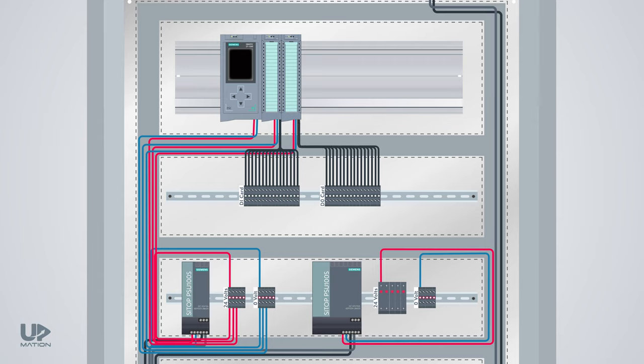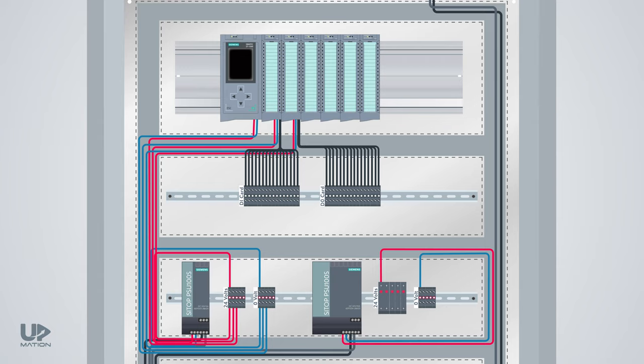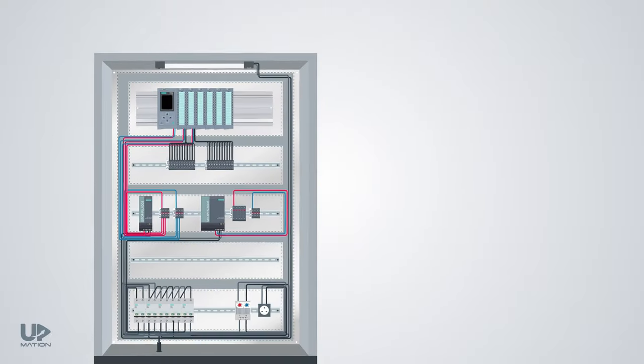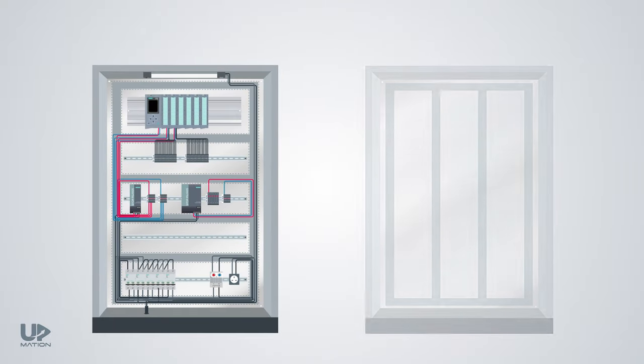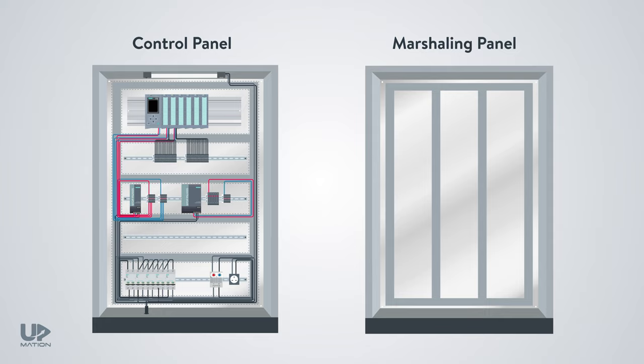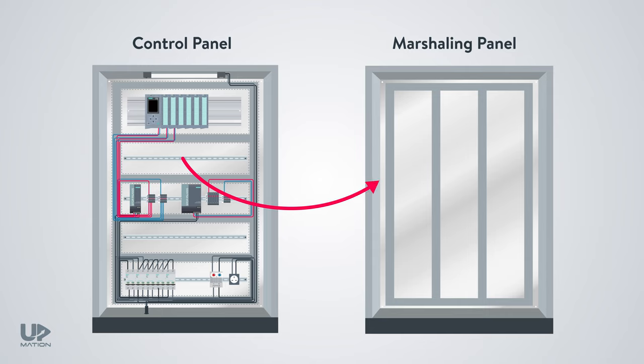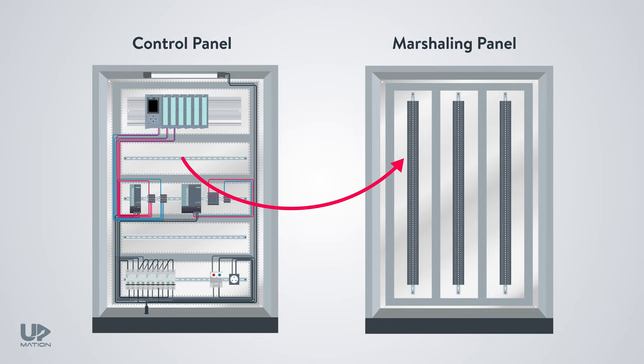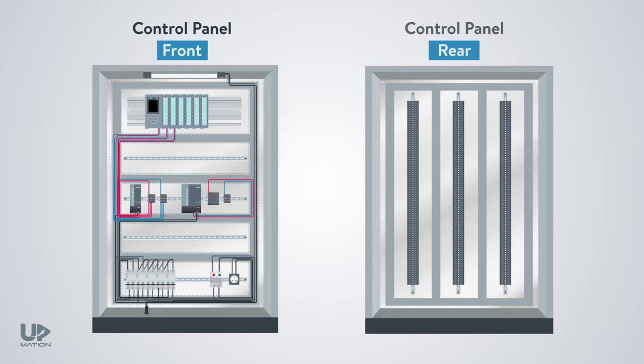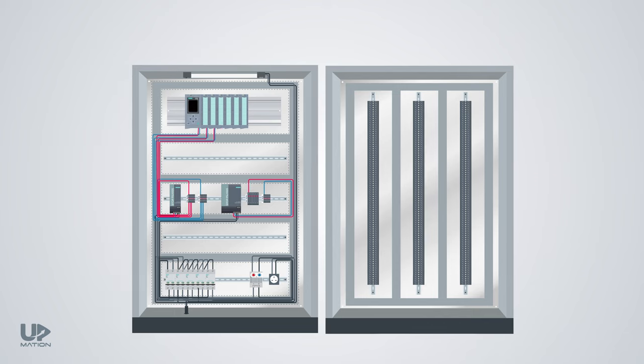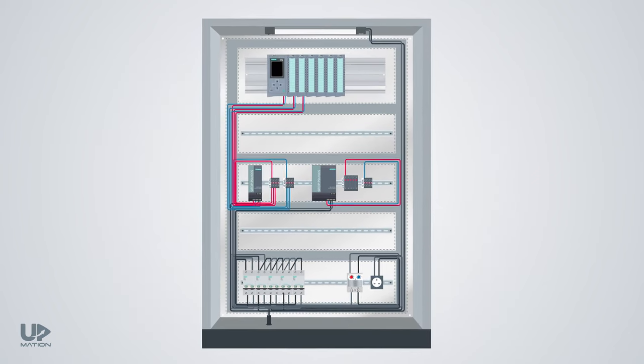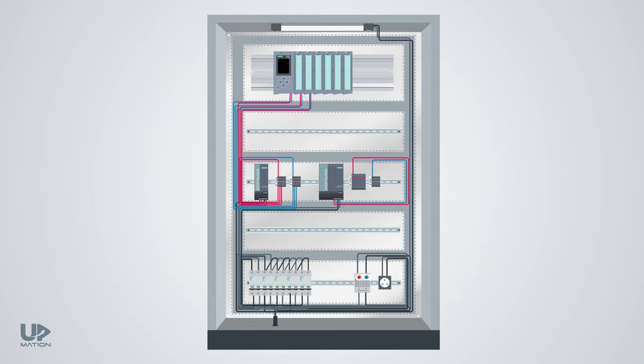You may be wondering when we have more DI or DO cards, we'll lack space for all of the terminal blocks. It is true, of course. If we have a huge number of inputs and outputs in the process, the layout of the panel gets completely different from what you see here. There should be another panel known as the marshalling panel. In this way, we'll transfer all of these terminal blocks to the marshalling cabinet. In some enclosures, the rear section of the mounting frame can be used as the marshalling part of the panel, so that we can merge the control and marshalling panels and save lots of space in the electrical or control room.